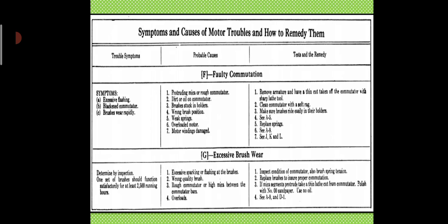Now the problem symptoms are excessive flashings, blackened commutator, and brushes wear rapidly. The problem causes: protruding mica or rough commutator, dirt or oil on commutator, brushes stuck in holders, wrong brush positions, weak springs, overload, motor windings damaged. Remove armature and have a thin cut taken off the commutator with a sharp lathe tool. Clean commutator with a soft rag. Make sure brushes ride easily in their holders and replace springs.